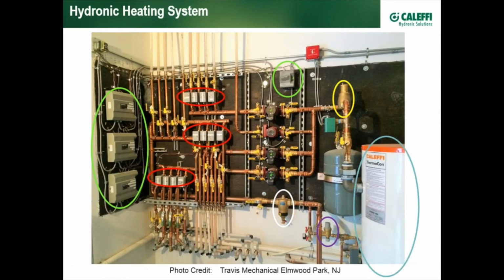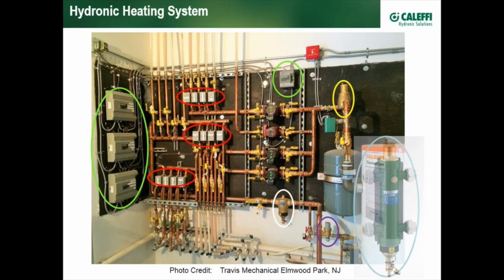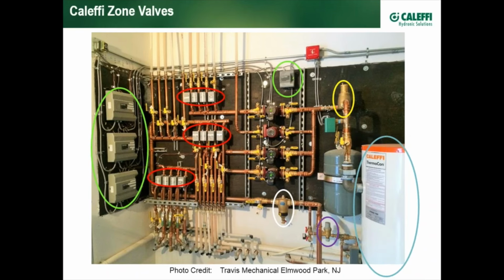Over here off to the right, we see a ThermoCon tank. This contractor has used this tank to not only provide hydraulic separation, so these pumps don't fight with one another, as well as perhaps the pumps on the primary side of the system, but the ThermoCon provides a thermal flywheel to prevent short cycling of the boiler in the event that any of these zones are with a small heat load. If there were no zones with small heat loads, perhaps the contractor would have selected from the many types of Caleffi hydraulic separators available to him.